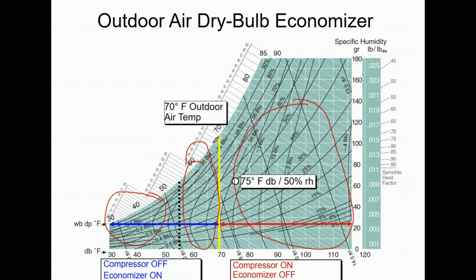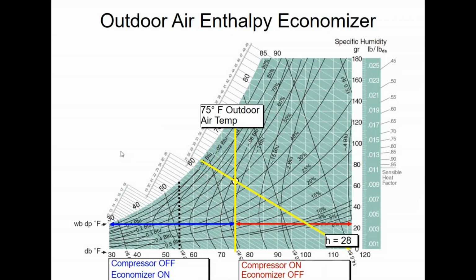There are some problems, which is specifically right over here. Actually, let me clear that so you can see. Specifically up in the top there, there's an issue right here. That tends to become an issue. Sometimes you'll hear me jokingly call it the triangle of death. When I get up to these higher humidities, true humidities, not percentage, but real, actual, specific humidity, at these elevated temperatures, high 60s, I tend to have some issues there. So we'll need to resolve that. Otherwise, we're going to have problem jobs, which none of us obviously want.